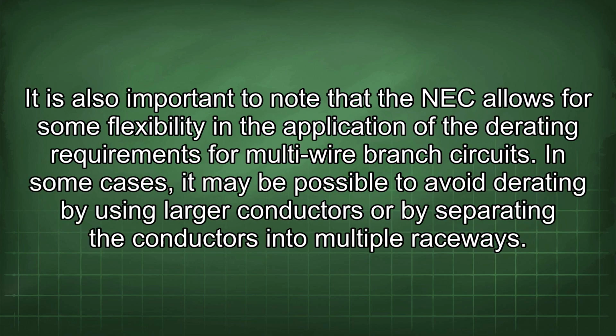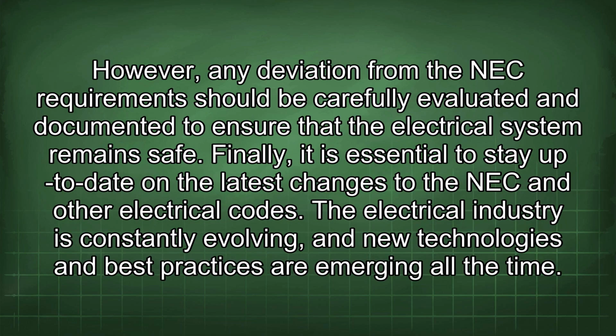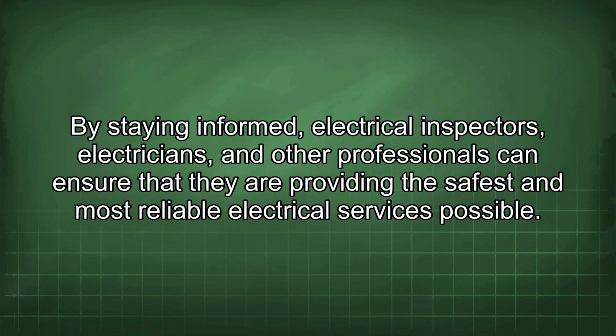It is also important to note that the NEC allows for some flexibility in the application of the derating requirements for multi-wire branch circuits. In some cases, it may be possible to avoid derating by using larger conductors or by separating the conductors into multiple raceways. However, any deviation from the NEC requirement should be carefully evaluated and documented to ensure that the electrical system remains safe. Finally, it is essential to stay up to date on the latest changes to the NEC and other electrical codes. The electrical industry is constantly evolving, and new technologies and best practices are emerging all the time. By staying informed, electrical inspectors, electricians, and other professionals can ensure that they are providing the safest and most reliable electrical services possible.